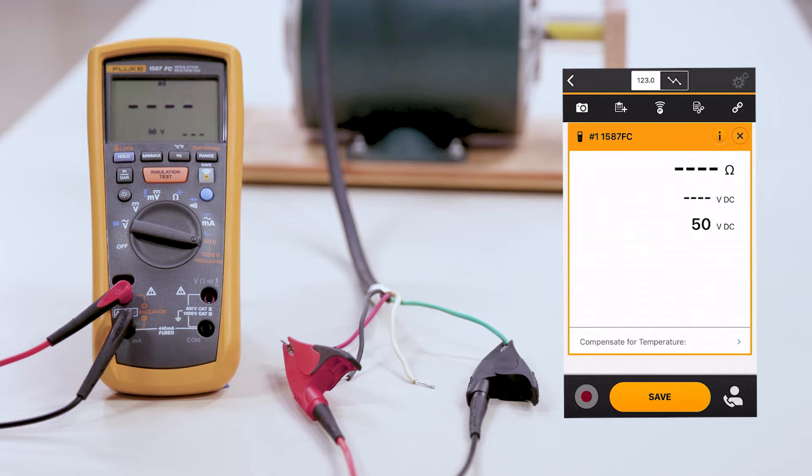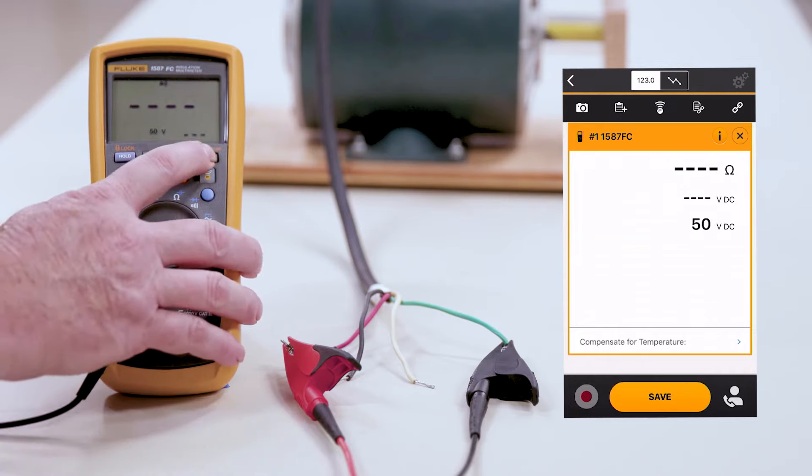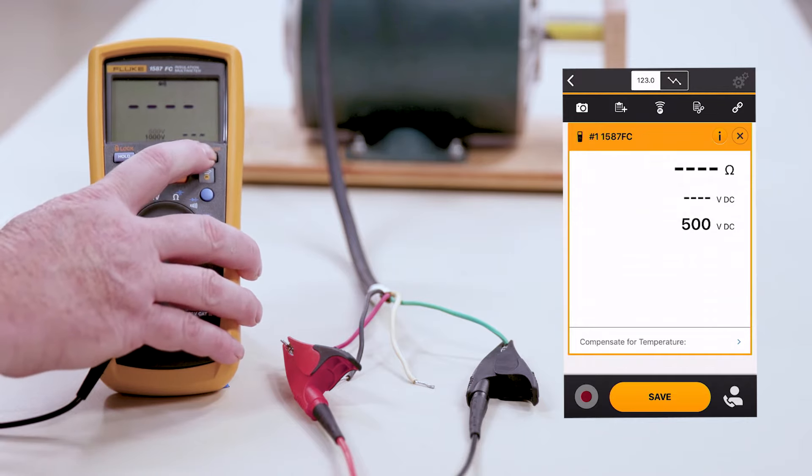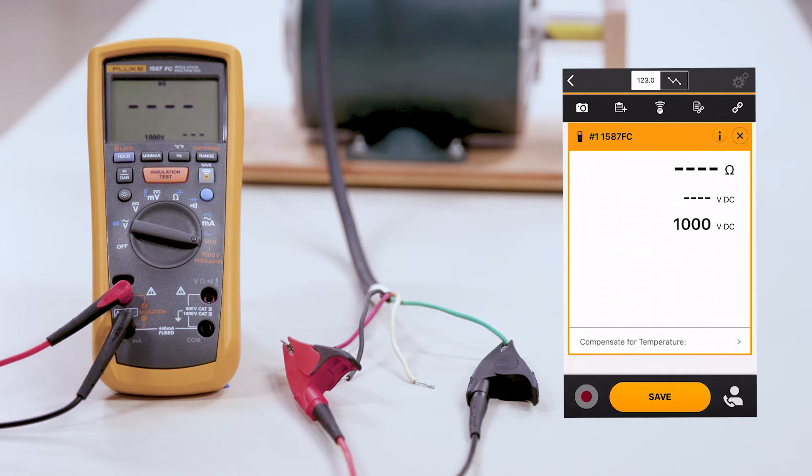By doing that, you'll hit the Range button. Now that we're at the 1000 volt test, we're going to check the windings of our motor to ground.